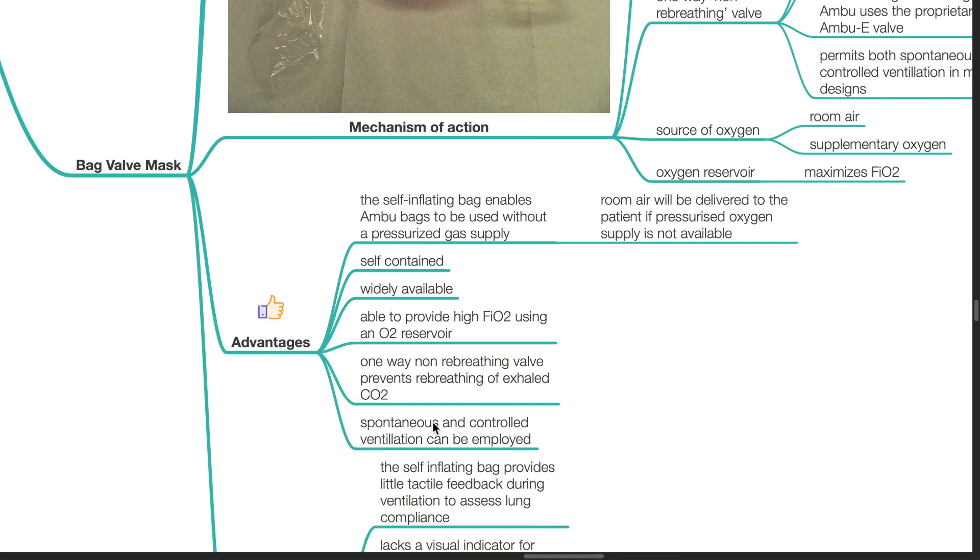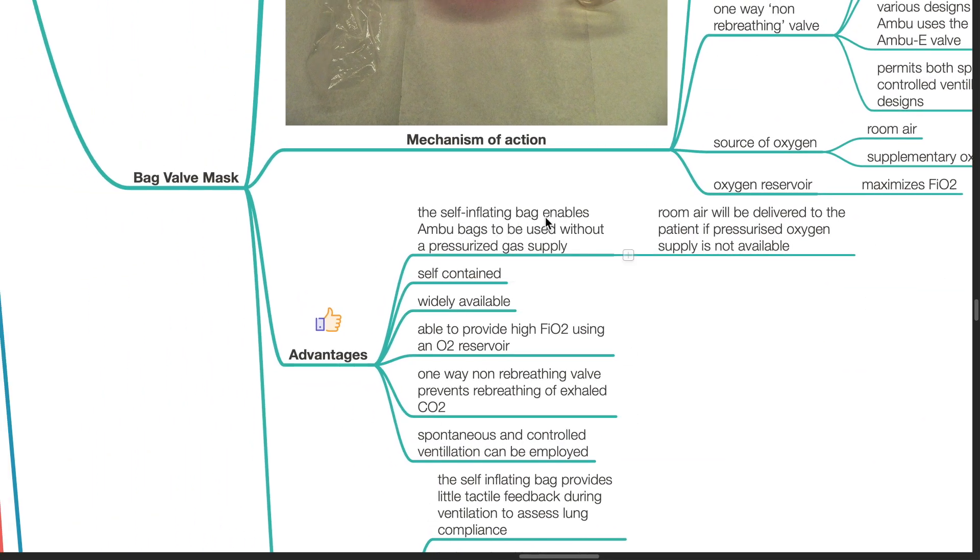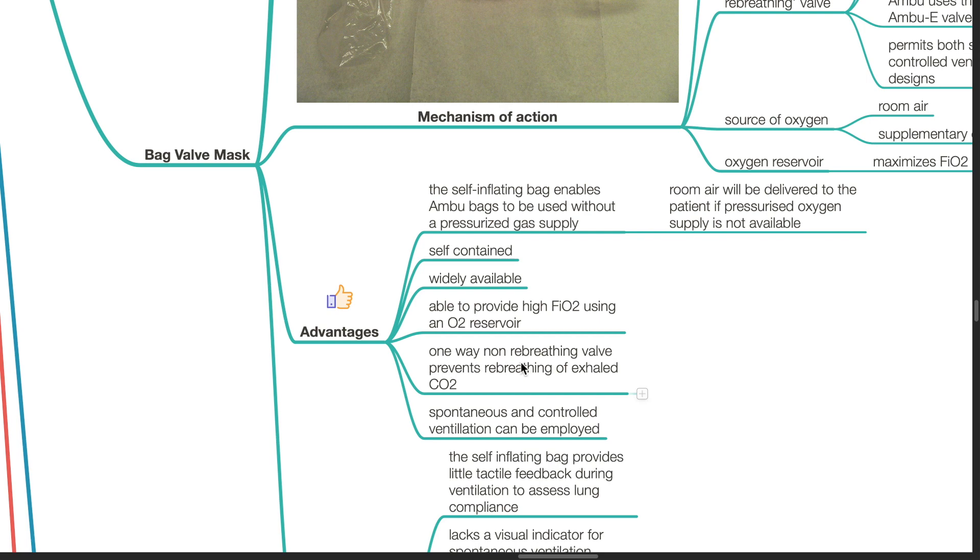Advantages. The self-inflating bag enables Ambu bags to be used without a pressurized gas supply. Room air will be delivered to the patient if pressurized oxygen supply is not available. It is self-contained, widely available, able to provide high FiO2 using an oxygen reservoir. The one-way non-re-breathing valve prevents re-breathing of exhaled CO2. Spontaneous and controlled ventilation can be employed.